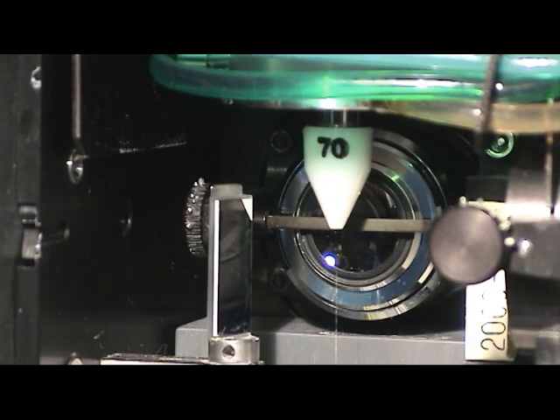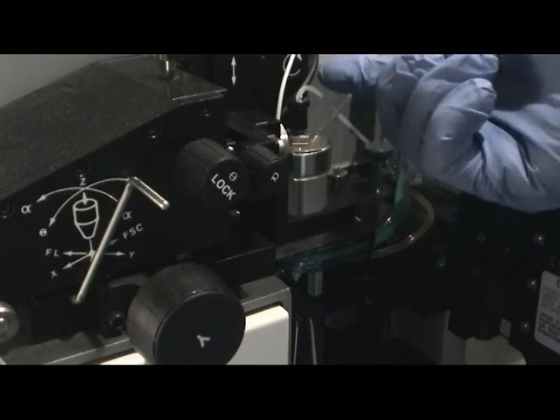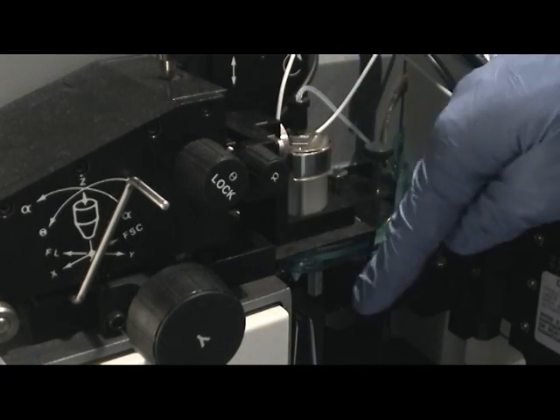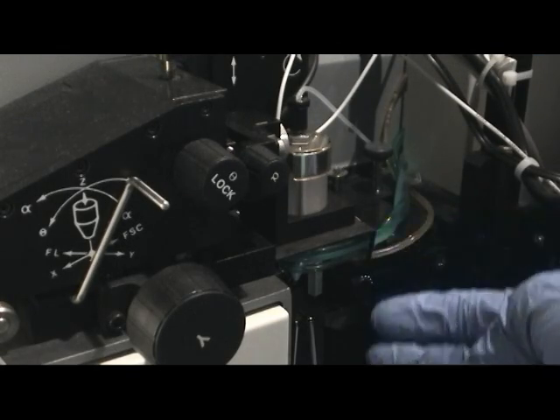The flow tip produces hydrodynamic flow. The purpose of hydrodynamic flow is to stretch out the sample stream into a row or column of single file cells.